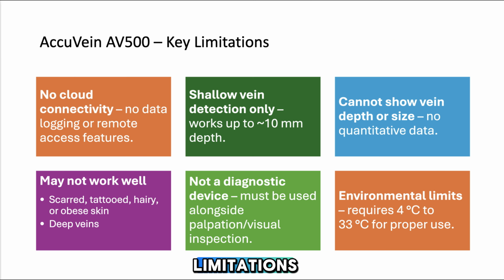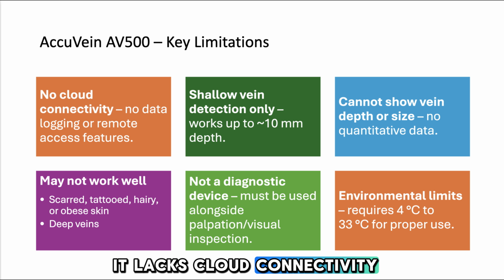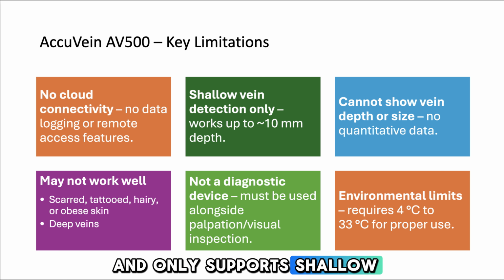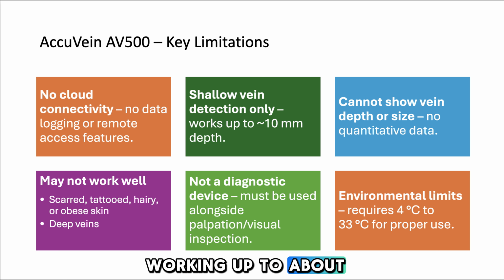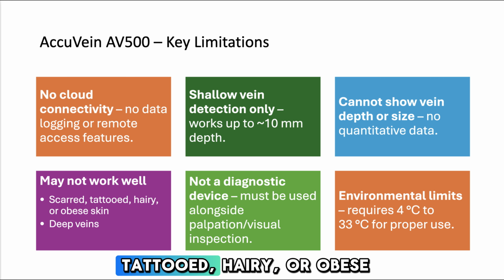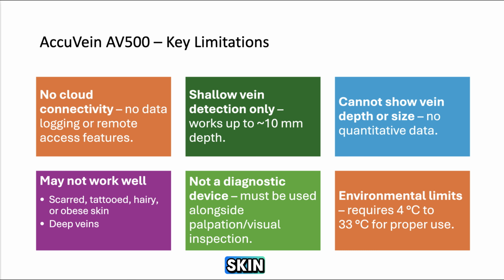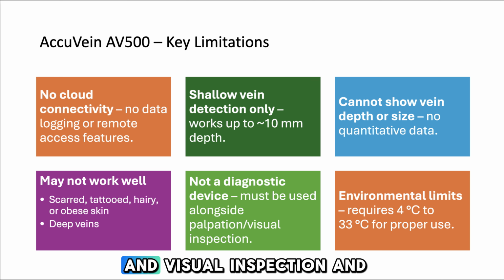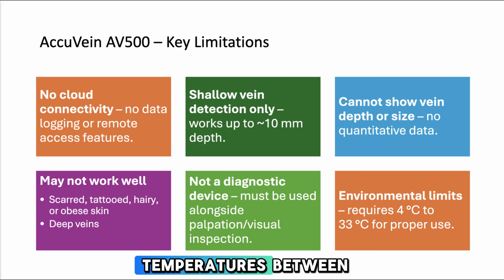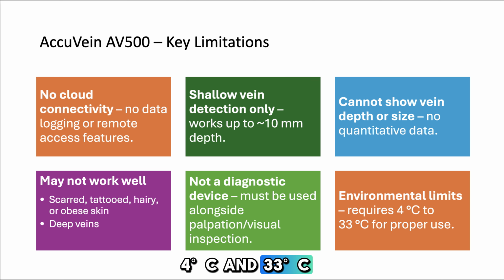The AccuVein has some limitations. It lacks cloud connectivity and only supports shallow vein detection, working up to about 10 millimeters deep, and can't show vein depth or size. It may not work well on scarred, tattooed, hairy, or obese skin and struggles with deep veins. The device is not diagnostic and should be used alongside palpation and visual inspection and in temperatures between 4 degrees C and 33 degrees C.